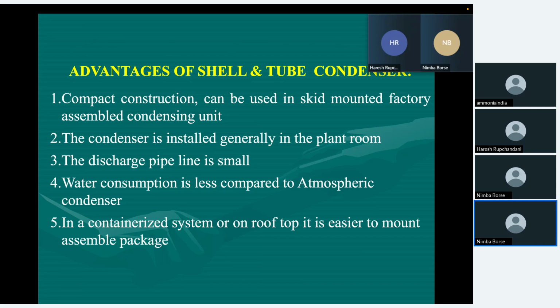In containerized systems or rooftop units, I have seen many ammonia units now installed in the USA on the rooftop. A package unit, completely of ammonia condenser, ammonia chiller, water-cooled chiller, is installed on the rooftop, and then even if ammonia leaks, it leaks into the atmosphere without affecting any occupancy areas. So these packages are becoming pretty popular now even in countries abroad. Europe, of course, uses a lot of ammonia, but Americans were a little bit against that. But now they have realized the importance of ammonia, and now they are using it also.